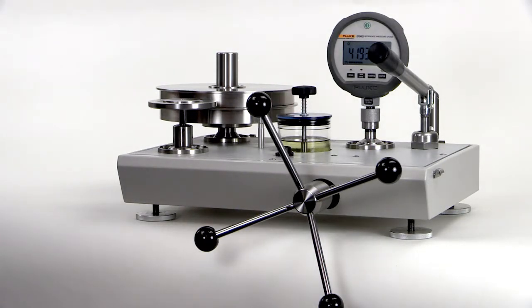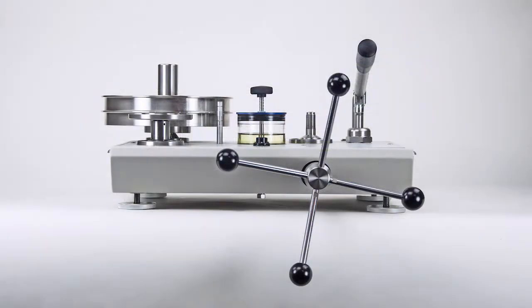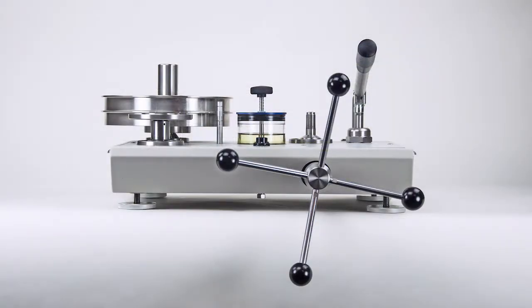Without this trimming, the user has to do some level of calculation. The concept of just adding up the pressures on the masses is completely destroyed. Therefore, Fluke Calibration performs this trimming at no additional cost to the customer.